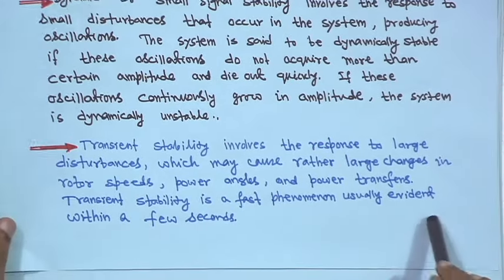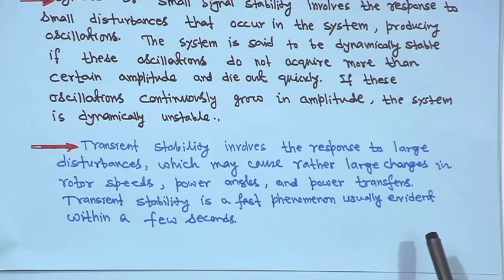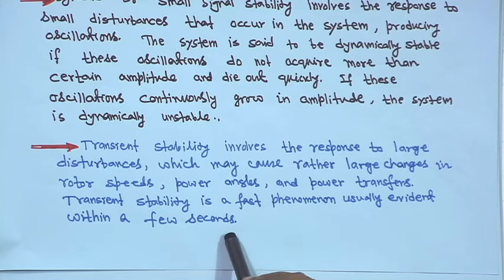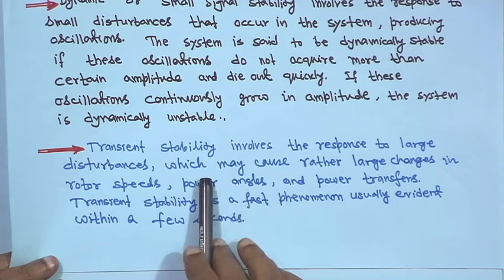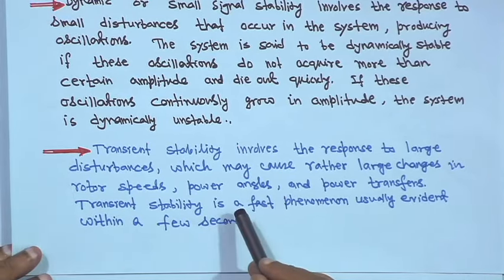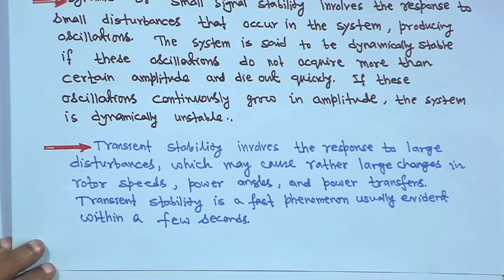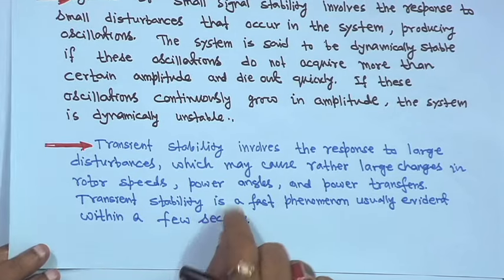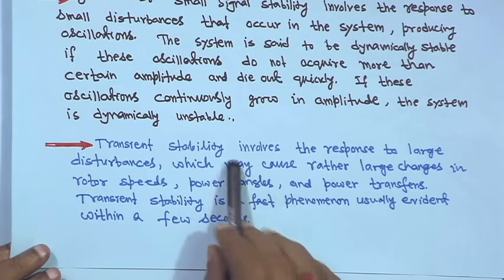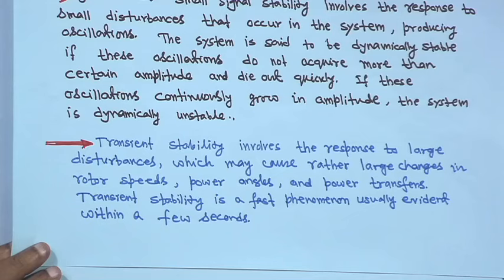Transient stability involves the response to large disturbances, which may cause rather large changes in rotor speed, power angles, and power transfer. Transient stability is a fast phenomenon and usually evident within a few seconds. Among these, transient stability is very severe because it is due to a large disturbance — for example, a three-phase fault or line-to-ground fault — causing large changes in rotor speed, power angles, and power transfer. For example, in a double circuit line, if there is a fault in one line, power transfer capability will change.